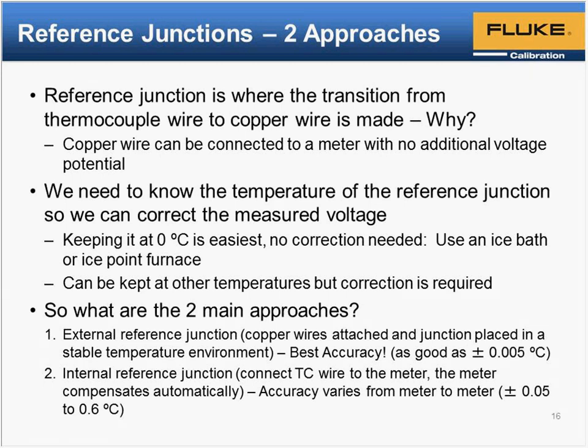We'll talk about how reference junctions are controlled. Keeping the reference junction at 0 degrees C is the easiest method, because the tables that you look at on the website or in the ASTM books or on any of the thermocouple manufacturers' websites, the temperature versus voltage tables, have the reference junction at 0 degrees C. So if you use an ice bath and you keep the junction at 0 degrees C, then you should see a voltage output that matches very closely with the tables.